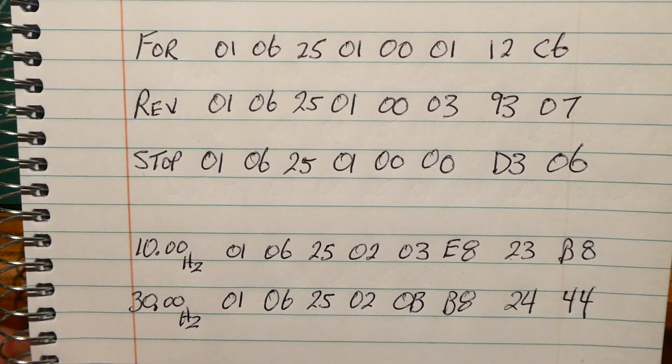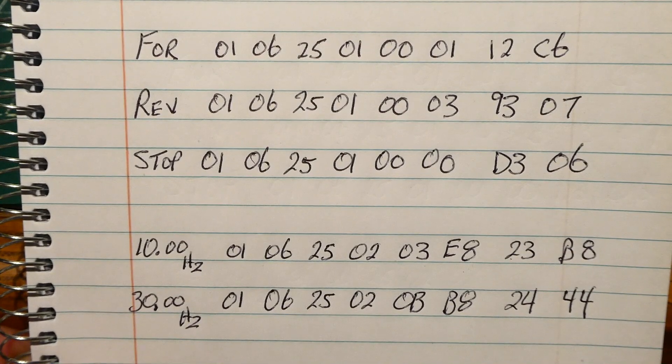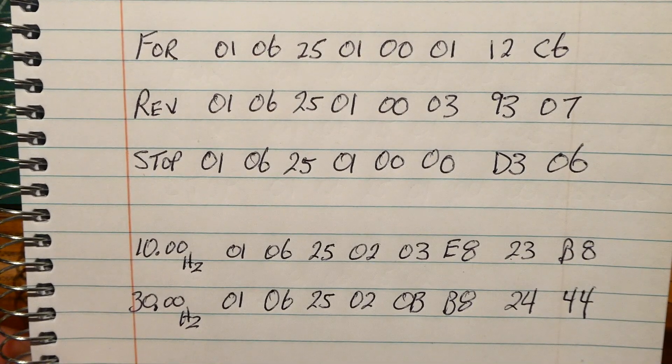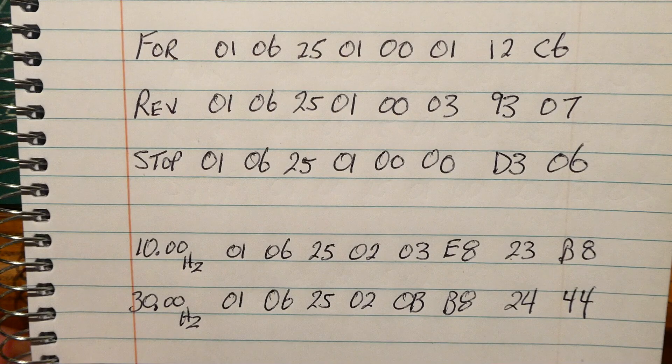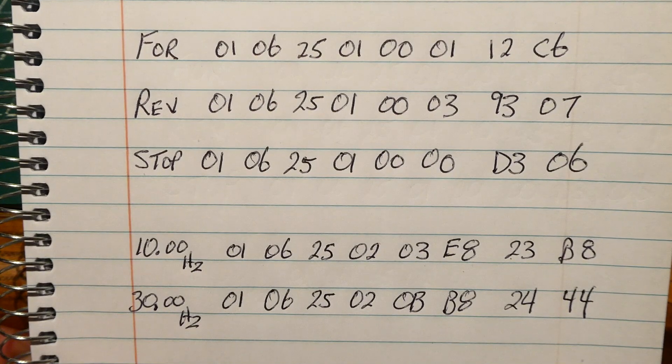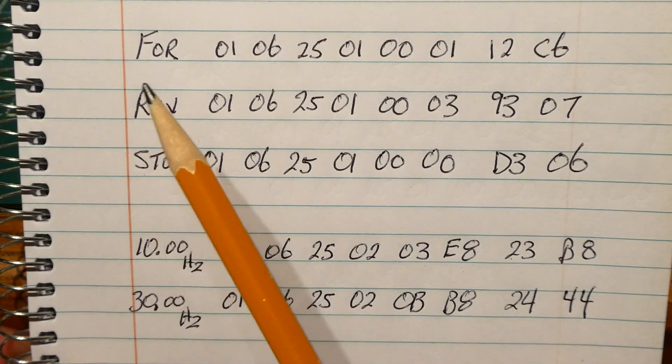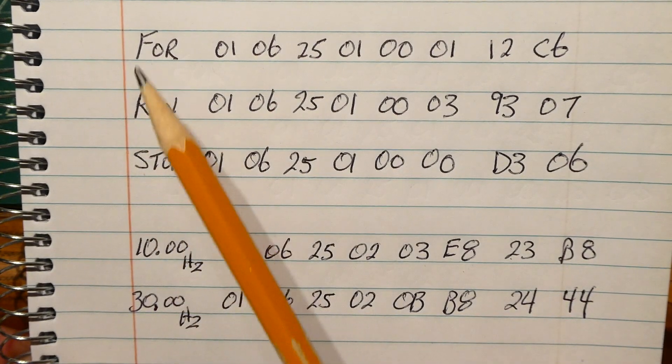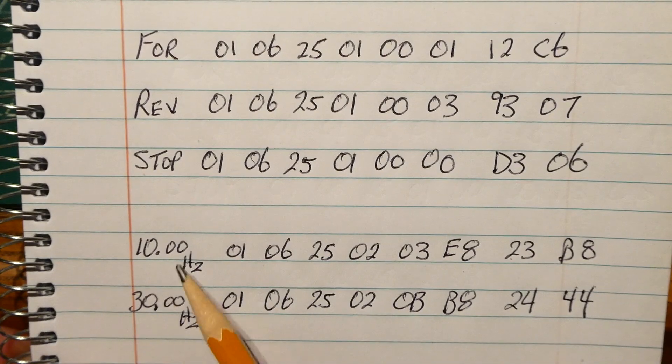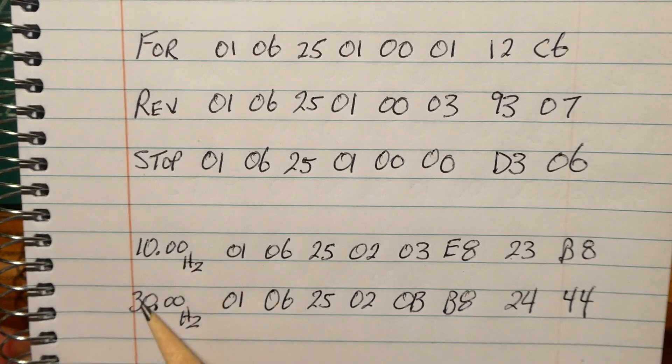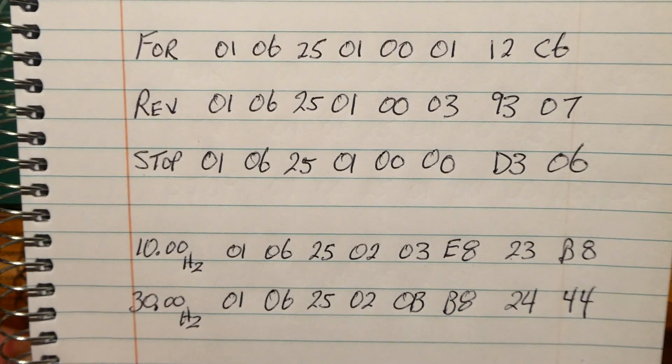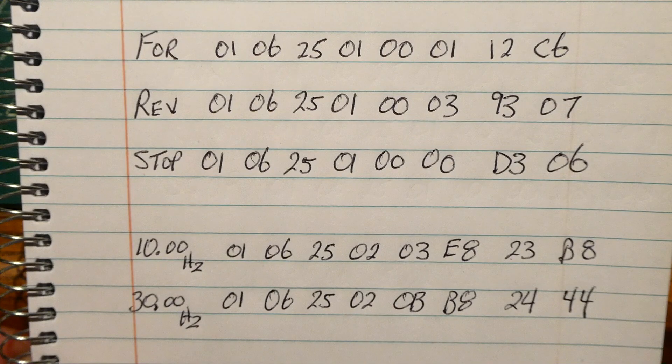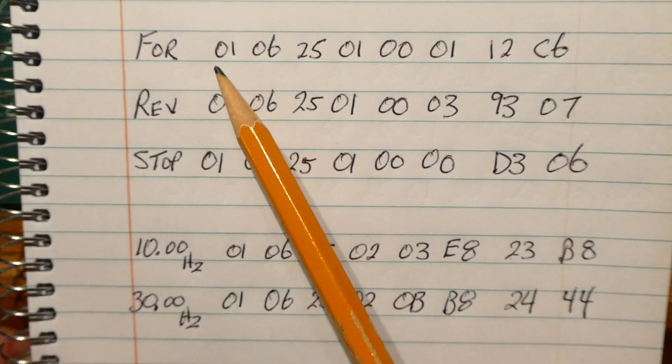Okay, to control the variable frequency drive using RTU Modbus, we send it a byte packet. Now each byte packet has eight bytes in it, and you can see my commands, I've got my direction, my forward, reverse, stop, and I've got my speed, 10 hertz and 30 hertz. Now each byte packet is eight bytes, and we can see them here.